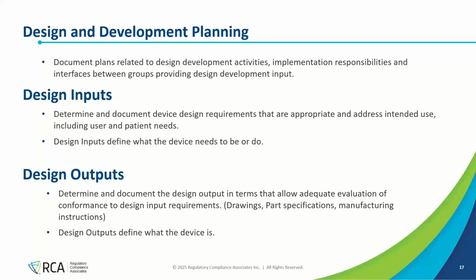Design inputs: the statement is you have to determine and document device design requirements appropriate to address the intended use, including user and patient needs. So the design inputs define what the device needs to do or be. It usually starts with user needs, high level from a user's perspective. The user wants the device to do this. Those get broken down into more specific engineering level requirements. That is usually how you capture that your intended use and your user requirements have been translated into your design input requirements that are engineering level and testable.